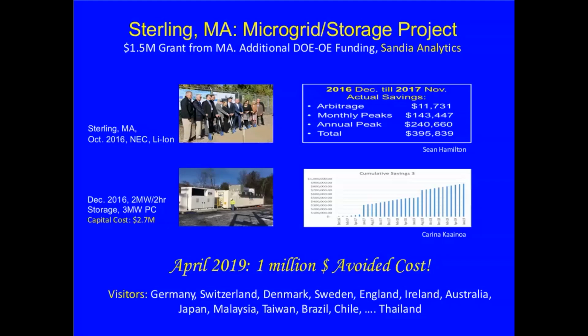So we put all the data on the computer at Sandia and came up with a business case for Sterling. It showed that by taking advantage of arbitrage on monthly and annual peak demand charges, we could provide a total of about $400,000 a year in payback. And they decided to do it that way.